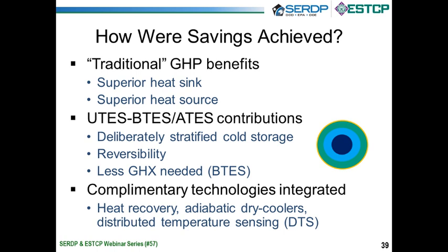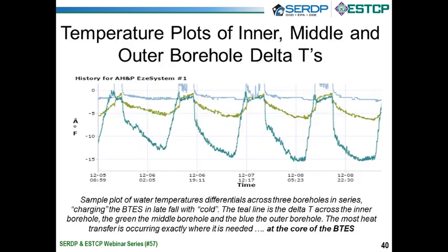Adiabatic dry coolers, I've kind of beat that to death, but they're more expensive than cooling towers. It'll always be cheaper to stick a metal box out there and then take the metal box and drip water down through, not hygroscopic, but hydrophilic PVC fill. But you use a pound of water for every 1,050 BTUs you've got to dissipate. So adiabatic dry coolers are more money, but they allow you to have a device that's much more optimized for sensible heat transfer and, when needed, can work in the evaporative cooling mode. And distributed temperature sensing, something I'm really excited about, and I'm going to hit here in just a moment if there's time.